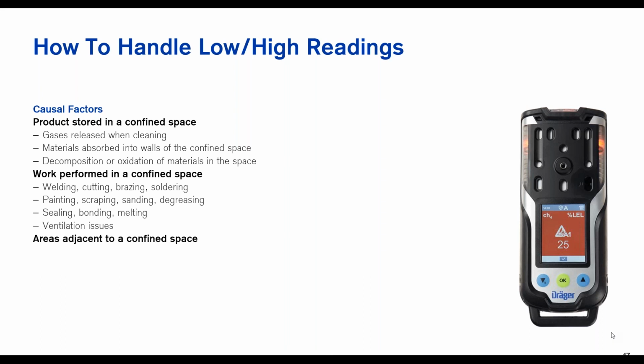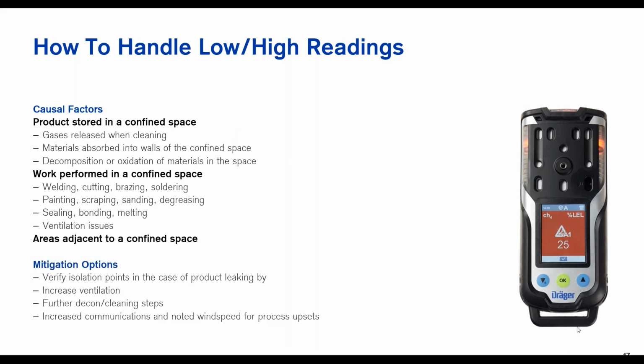How do we mitigate those issues? How do we verify our isolation points are causing that issue to leak by? Has my ball valve that I've locked out actually caused that to leak past it? Do I need increased ventilation in place? Do I need to add a second fan, or use ventilation fans in tandem, one using positive pressure forcing air in, and one at the bottom of the confined space using negative pressure to suck that contaminated air out? Do I need to go in and clean it out? A lot of different things here to focus on, looking at wind speed, process upsets, all those things we're taking into mind based on that site-specific hazard assessment, to decide how we're going to mitigate that.